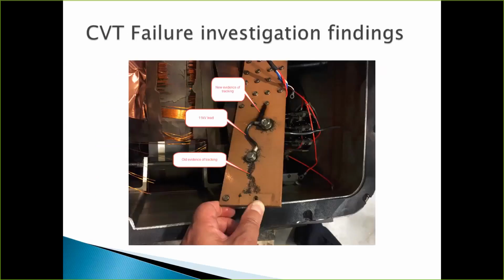Okay, here's what happened. We were interested in the analysis, the extended condition of the device. So this is the bottom section. Typically, this would be oil filled. This is your inductive transformer we looked at earlier. Some of this is your ferroresonance suppression circuits. What we saw here was really astonishing. This is the 11 kV lead that you have. Mind you, this is in oil, so it doesn't arc. But what you saw was evidence of old arcing in the tank down there. An old carbon path was being built. And you saw a new, hard bolted, hard fault there.